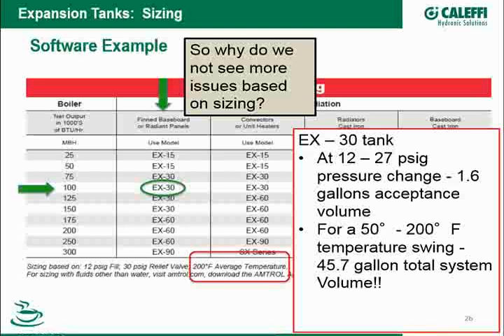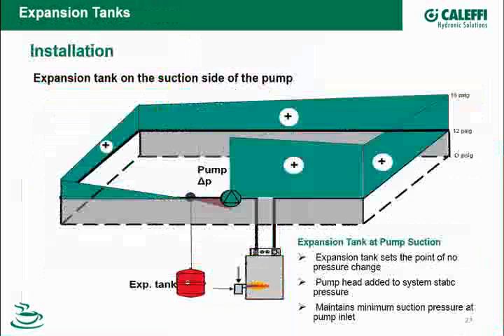Now, we've talked a little about this in bits and pieces: the decision of where I'm going to put the expansion tank into the system. The point of no pressure change is one of those topics that has been well discussed within our industry over the past 15 to 20 years. So when I'm putting that expansion tank in there, I have to look at the relationship between the expansion tank and the pumps in the system. I choose a pump or a circulator.